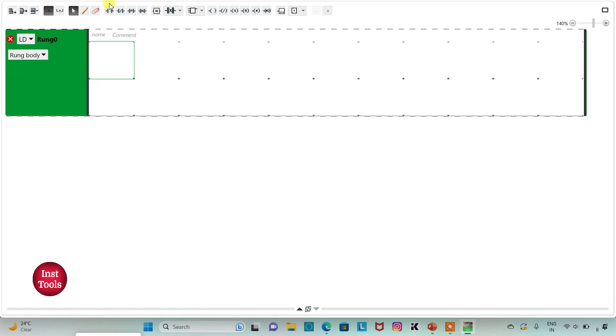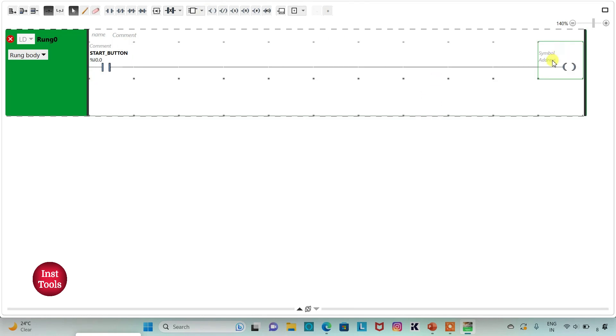Firstly I will insert a normally open contact. I will assign address to it as I0.0. I will also add a symbol to it as start button. And then I will insert a coil here. I will assign address to it as Q0.0. I will also add a symbol to it as conveyor.